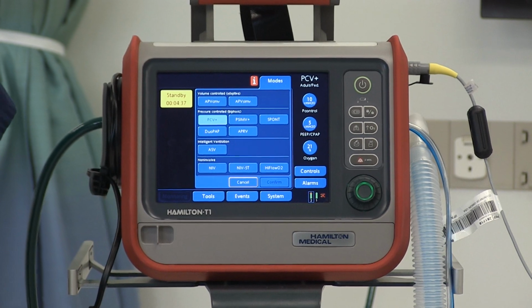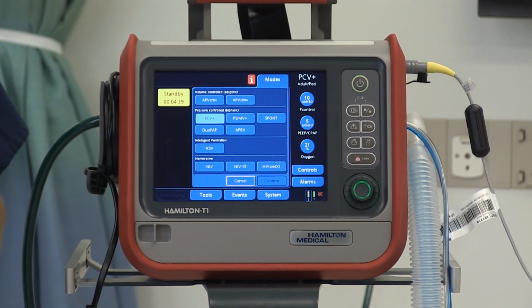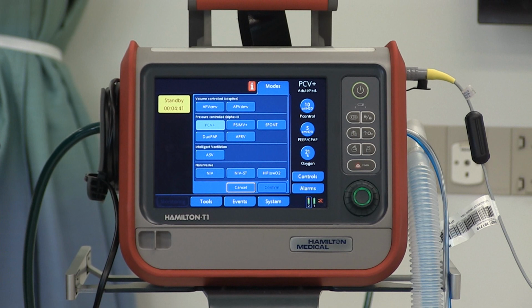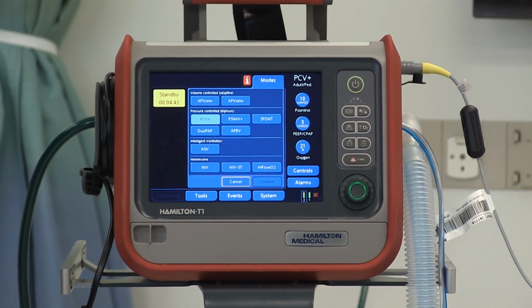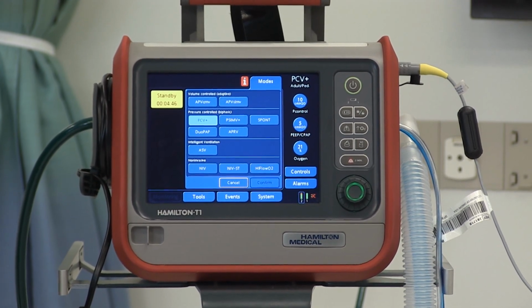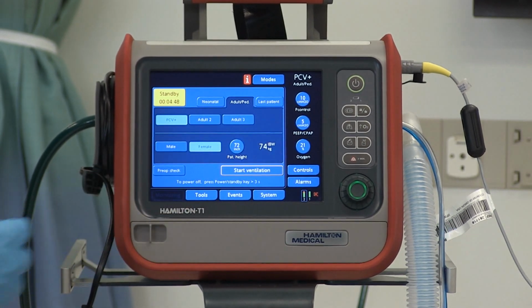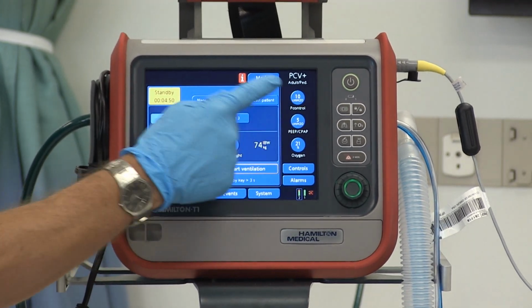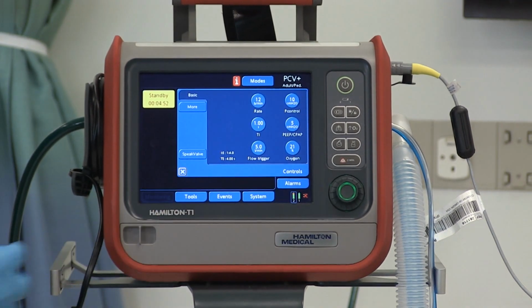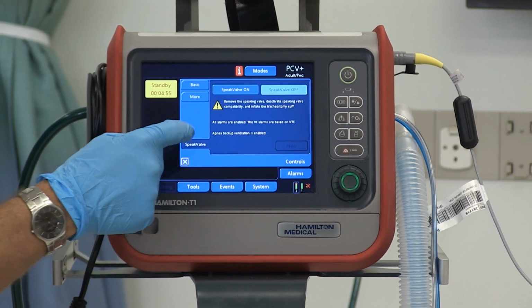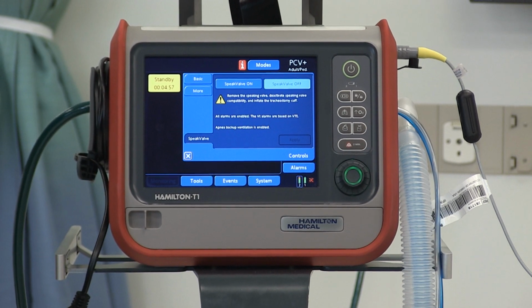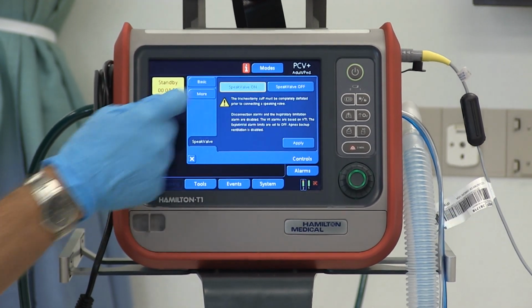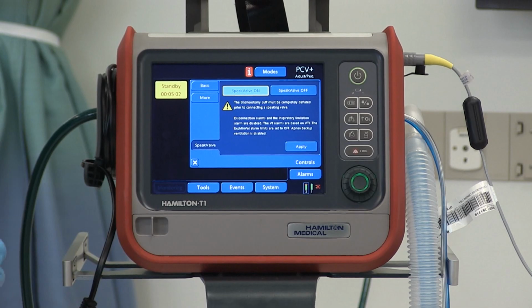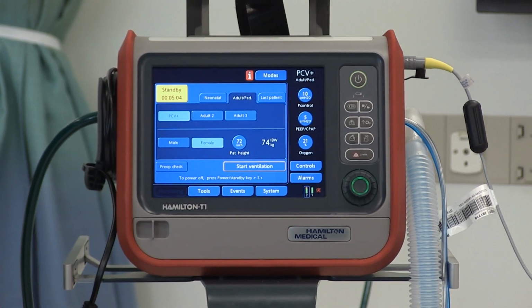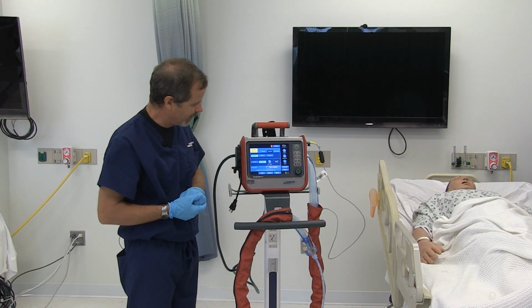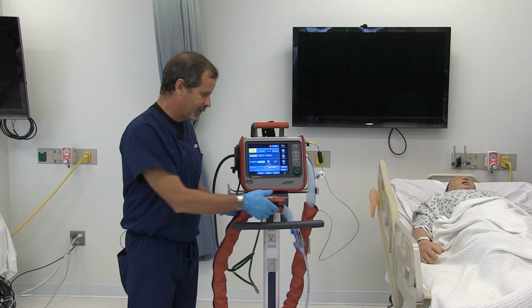Below that is another section for non-invasive modes. We have NIV, NIV-ST, that's with a backup rate, and we have high flow oxygen. Also in our pressure control mode, we have speak valve. You can see I'm in pressure control mode now. If I open the controls window, activate speak valve like this. Activate on and then confirm. We're not going to use that mode right now, so I'm just going to X that out. We're still in pressure control ventilation, and I can start the ventilator.